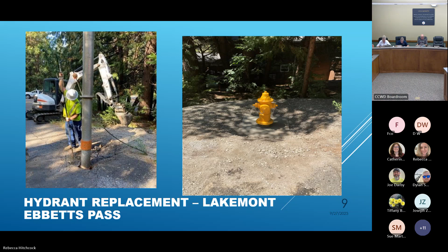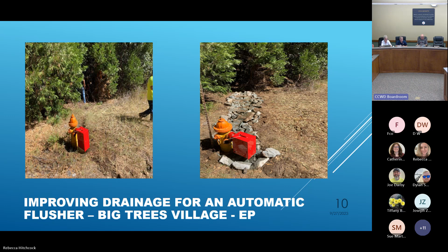It's also about optimizing water age on Ebbets Pass, which is quite a distribution system, and water age can be an issue. Our crews survey the distribution system and move automatic flushers to where they see optimal placement. We then work with our construction crew to install, in this case, riprap to make sure we don't negatively impact anyone's property when it discharges. This flusher can automatically discharge up to about 8,000 gallons a day, reducing water age in the system and improving overall water quality during periods of low use.